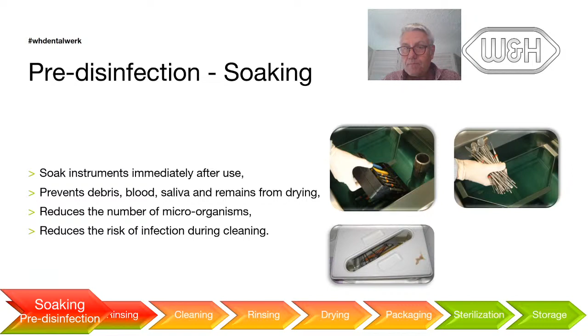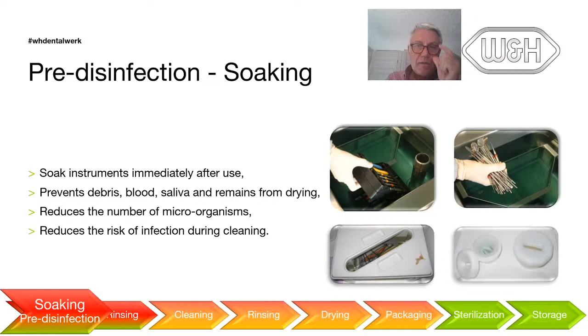Second thing, inside these debris, stains, remains, tissues, bacteria will continue to grow. If you think that every half an hour you will double the number of microorganisms on your instruments, you may even compromise sterilization. If there are too many microorganisms, it's going to be impossible to sterilize. I know it sounds strange, but now the very good reason for this is not here. We don't want only to stop the growth. We want to start killing. We talk about the log of 5, a reduction of 10 to minus 5, so 100,000 times the population of microorganisms. And by doing so, it is also safer for your staff, because after this you're going to transport, manipulate, clean, maybe manually clean the instruments. So you put your personnel at risk if you don't do this properly.